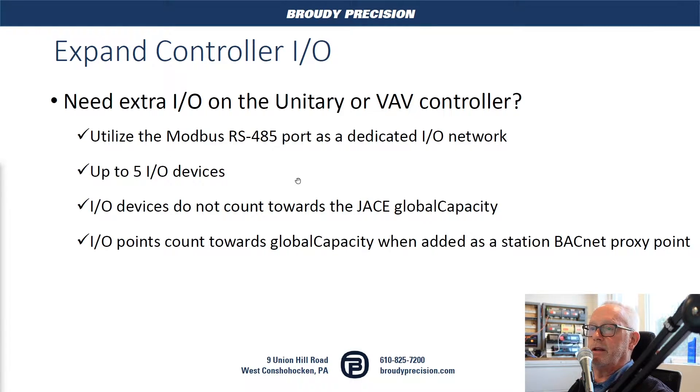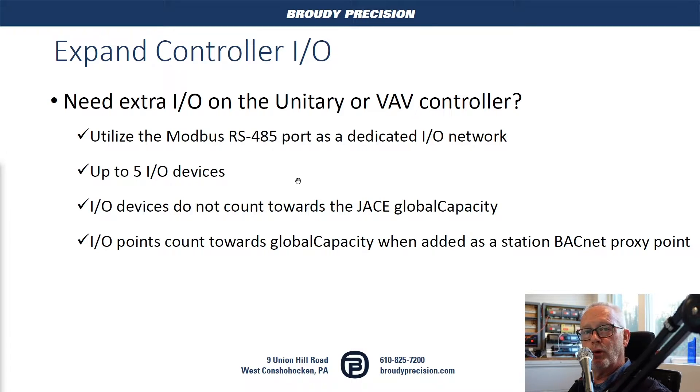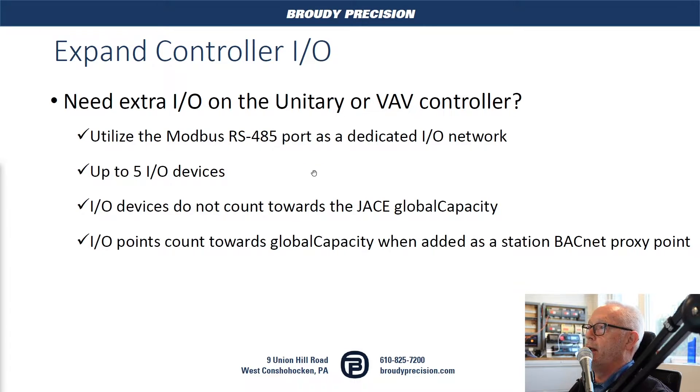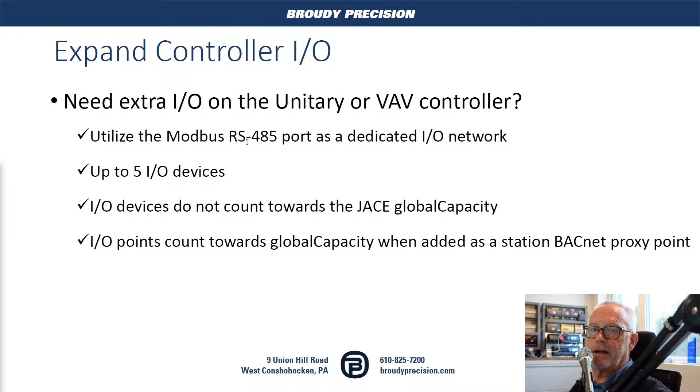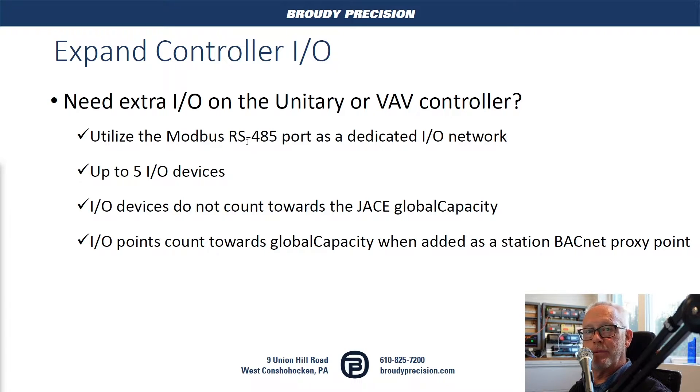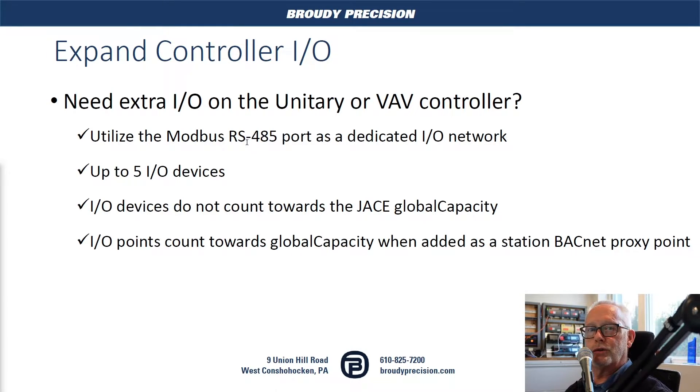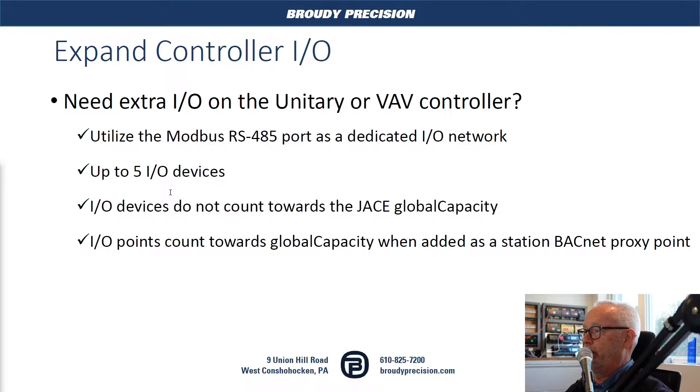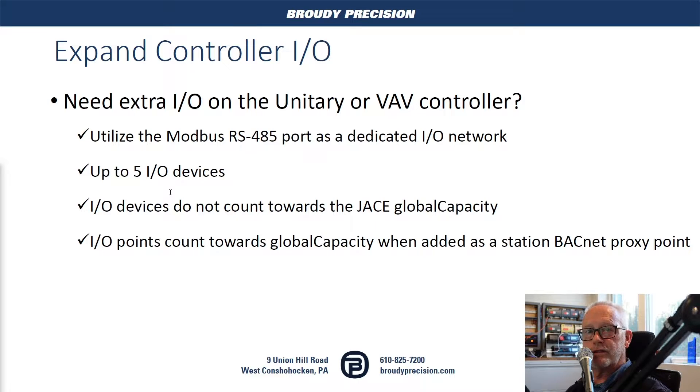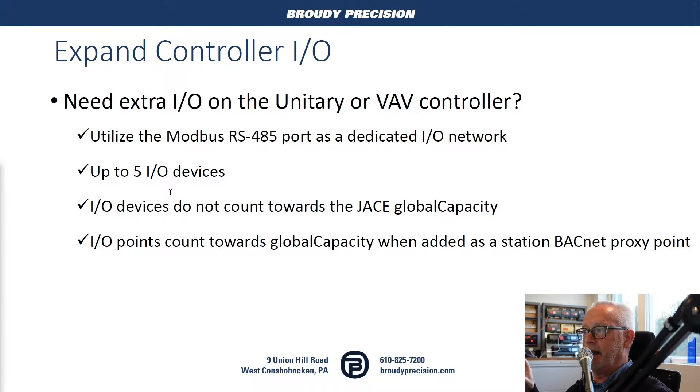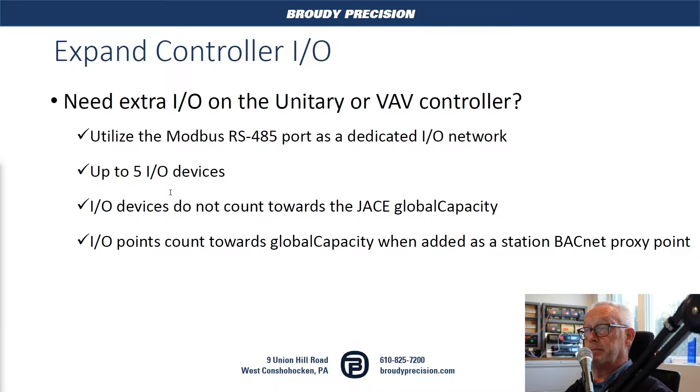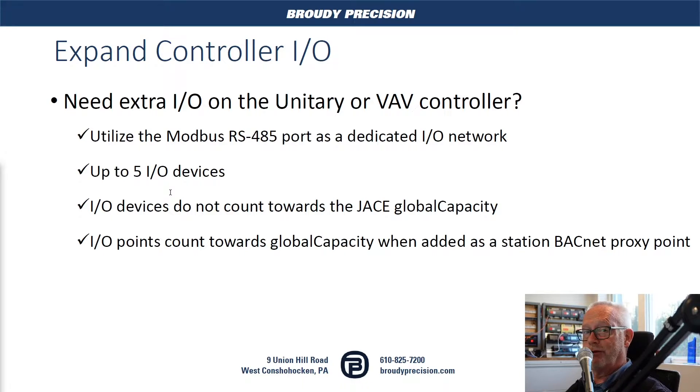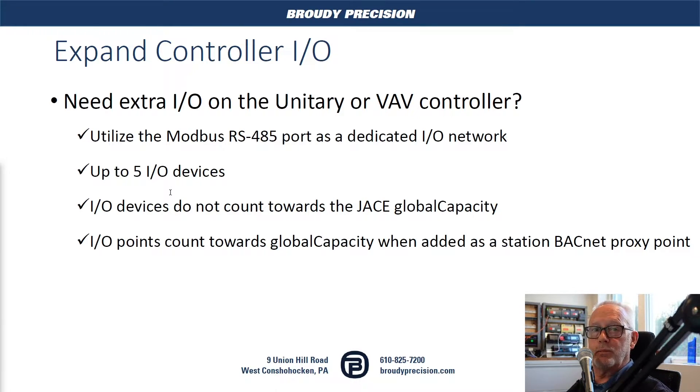On the controllers, there's times when you need to pick up a few extra points, whether monitoring or for control, and this port will allow this to happen. You can utilize this 485 port and make it a dedicated I/O network. The Modbus devices do not count towards the JACE global capacity. It's the points that once you create a BACnet point and expose it as a proxy point within the station that goes towards the global capacity. For devices, it's not at all.